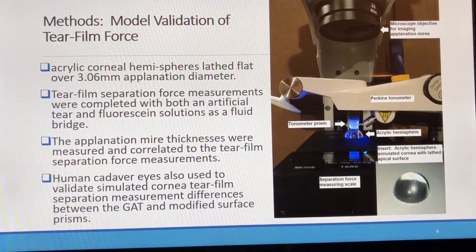We wanted to quantify an isolated tear film adhesion and validate the theoretical findings. We started by producing an acrylic corneal model lathed flat over the central 3.06 millimeters to simulate the conditions of full applanation. We then applied an artificial tear and measured the force to separate the tonometer prism from the acrylic cornea. Applanation mire thickness was simultaneously measured as a possible contributing factor.